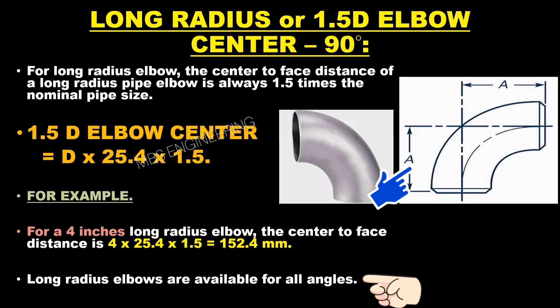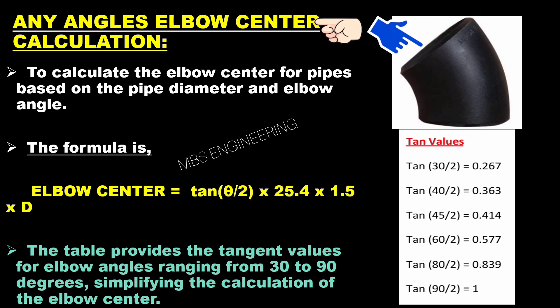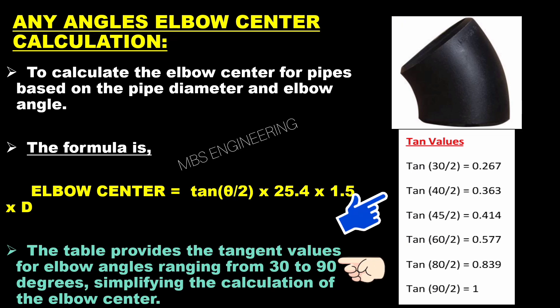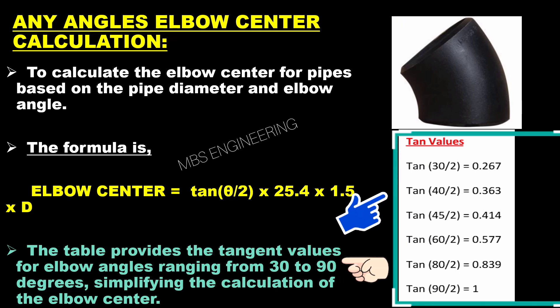Long radius elbows are available for all angles. To calculate the elbow center for any angle, the formula is: Elbow Center = tan(θ/2) × 25.4 × 1.5 × D, where θ is the elbow angle and D is the elbow diameter in inches. A table provides tangent values for elbow angles ranging from 30 to 90 degrees, simplifying the calculation.